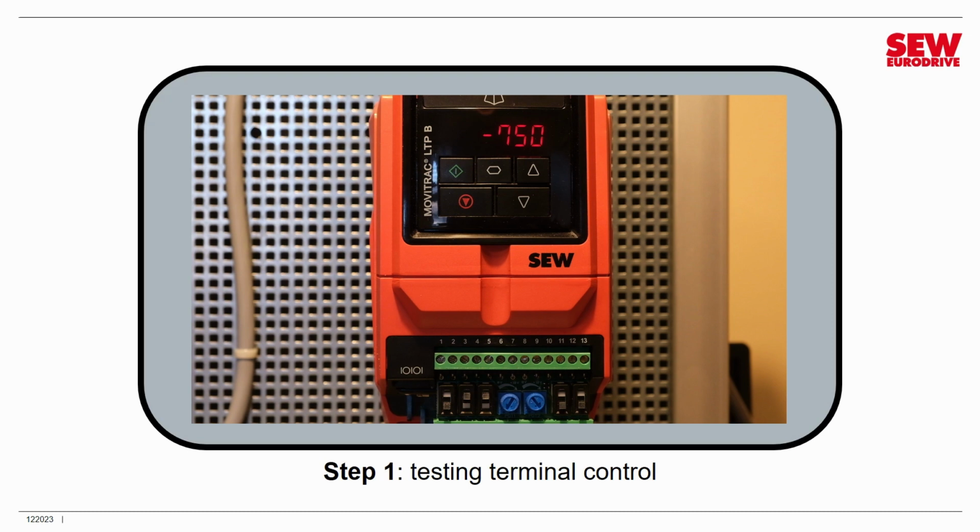Let's create a field bus fault by disconnecting the network cable. So we'll remove it there. And after a 1 second delay, you can see it goes into shutdown as it's programmed to do. Notice it doesn't fault. It's not supposed to. It's just supposed to ramp down and stop. So it looks like everything is working as expected.